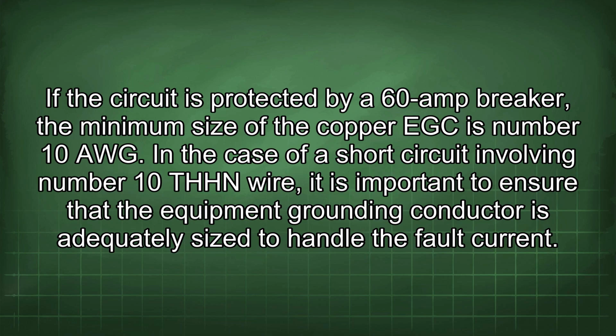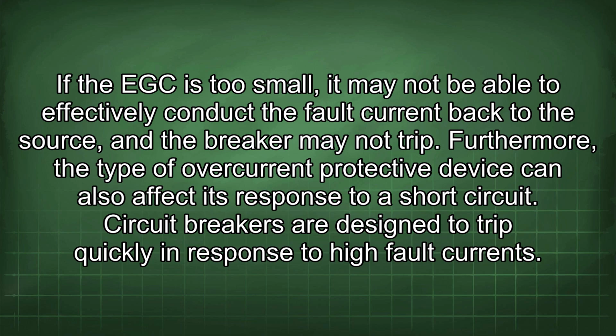In the case of a short circuit involving number 10 THHN wire, it is important to ensure that the equipment grounding conductor is adequately sized to handle the fault current. If the EGC is too small, it may not be able to effectively conduct the fault current back to the source, and the breaker may not trip.